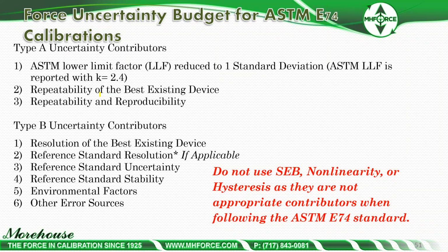But if we're looking at ASTM calibration, the biggest mistake is people say, hey, I'm going to use SEB, nonlinearity, hysteresis. This comes from assessors too. It's coming right out of that NCSLI RP12 document, and it's not right. If you're using ASTM, you don't care. We don't care about SEB. We don't care about nonlinearity or hysteresis. We just don't care, because the standard is going to give us a quadratic. They're going to give us coefficients to fit a curve, and all that goes away. If we use those coefficients, we're going to match that force point almost exactly.